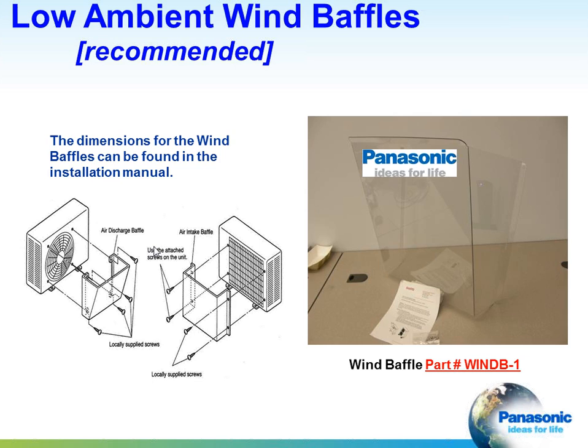You want that wind baffle, so if you have a stiff breeze, you don't have too much cold air going over those coils and fighting off your gas coming back that will be defrosting your coils. The other reason that you need wind baffles is, again, if we have a stiff breeze and you're in partial capacity, whether in heating or cooling, the outdoor fan is going to be turning at a relatively low RPM. A stiff wind will speed that fan up, and that will affect the capacity control of the unit. When the unit sees that fan turning faster, it will react.